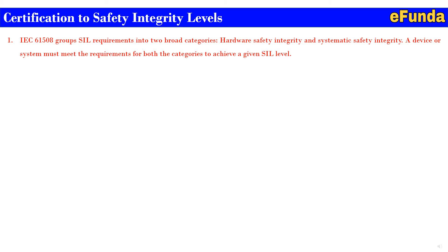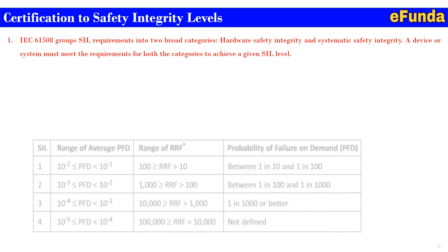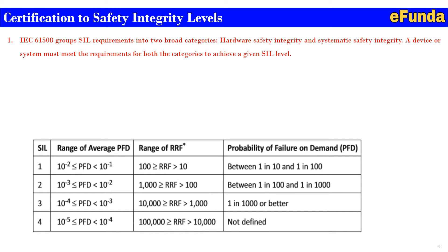Certification to Safety Integrity Level: IEC 61508 groups SIL requirements into two broad categories — hardware safety integrity and systematic safety integrity. A device or system must meet the requirements of both categories to achieve a given SIL level as required by the operation team. One can refer to the table where SIL ratings SIL 1, SIL 2, SIL 3, and SIL 4 are defined along with the range of average PFD values and risk reduction factors.